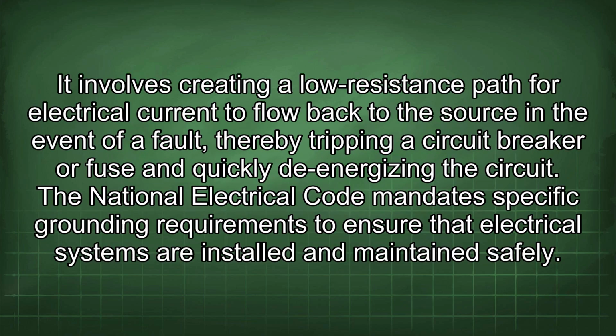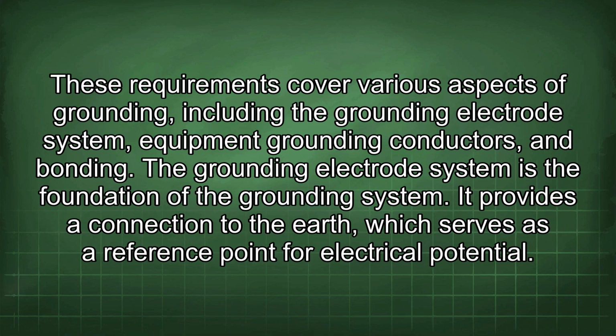It involves creating a low-resistance path for electrical current to flow back to the source in the event of a fault, thereby tripping a circuit breaker or fuse and quickly de-energizing the circuit. The National Electrical Code mandates specific grounding requirements to ensure that electrical systems are installed and maintained safely. These requirements cover various aspects of grounding, including the grounding electrode system, equipment grounding conductors, and bonding.